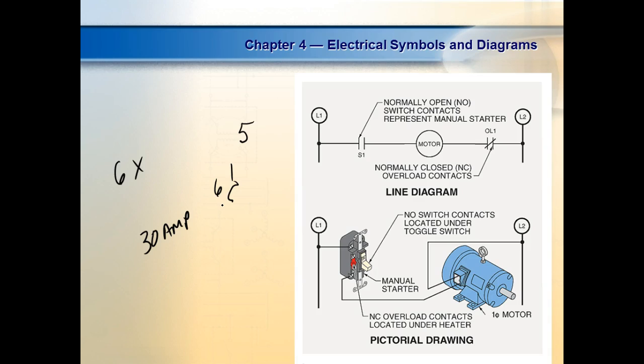So when you fuse the motor, it's always like 125 to 150% of the maximum current that will be drawn. So it means I would have to fuse that thing to 35 or 40 amps, right? You understand? So what happens if the motor doesn't start? It's going to sit there and burn up, because it's only supposed to handle that start current for a short amount of time. So we have to have some method to keep that motor out if it draws over current over a certain amount of time. And this is what your overloads do. So your overload kicks out the motor if the motor doesn't start.